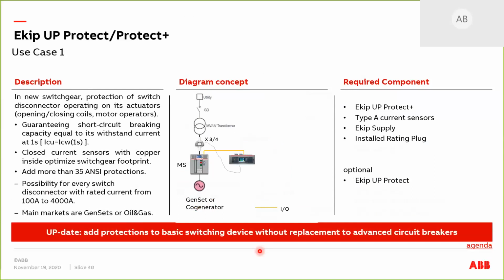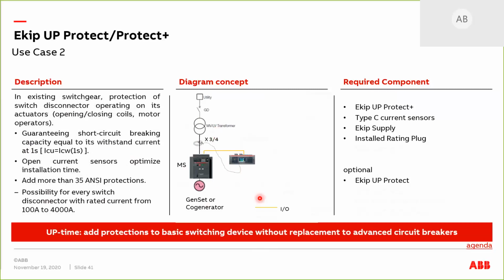Okay, with the protect function, you will be able to have the guarantee of the short circuit breaking capacity equal to its withstand current. So it can send a signal to the breaker so that it will trip, aside from the monitoring. With this one, there is the current sensor that is connected to the EKIP. Next is the use of the Type C or the Rogowski coil. So it's the same situation.